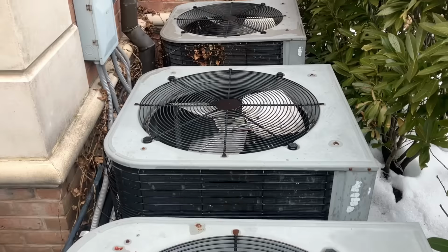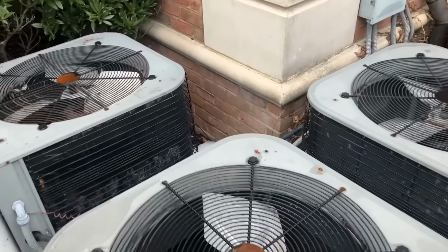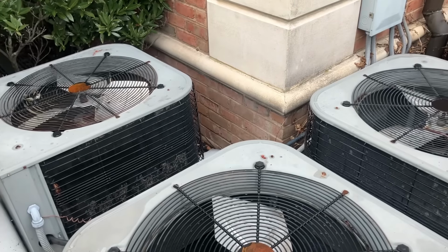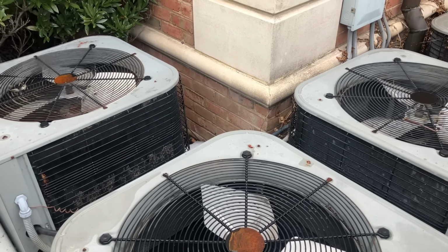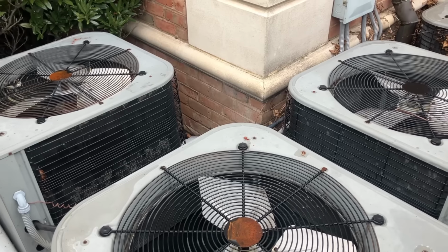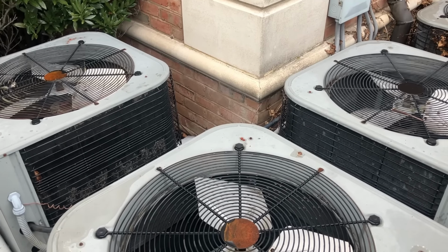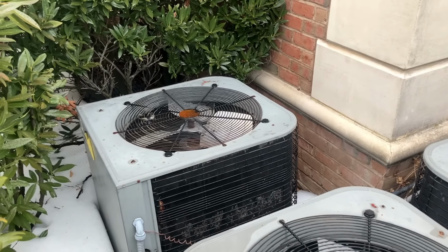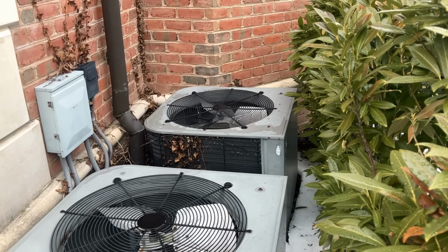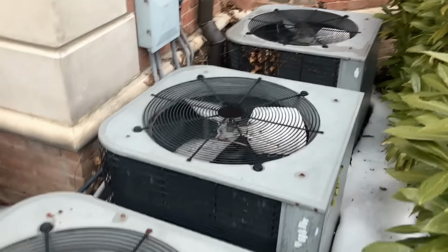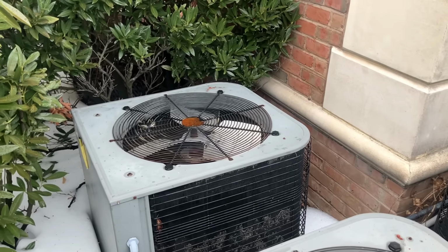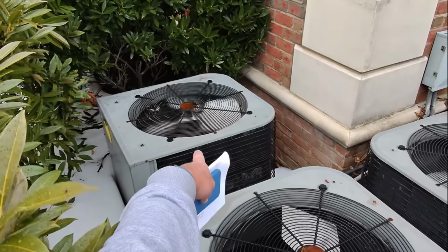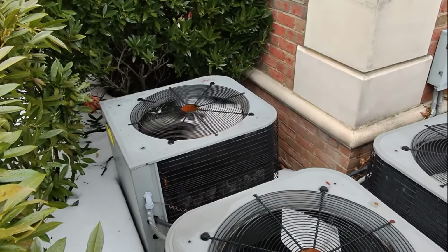Eeny, meeny, miny, mo. Folks, it's not a guessing game. We have a residential client here with this massive estate. We just can't guess which one it is. We're going to verify which one it is by turning the thermostat on to cool, setting it for a lower temperature than the ambient temperature the thermostat is reading, and we'll know exactly which one we're decommissioning today. Is it the one with the dead bird? Is it this one, that one, or that Lennox R22 central AC system? Which one do you think, folks? If you guessed that one, you guessed correct.